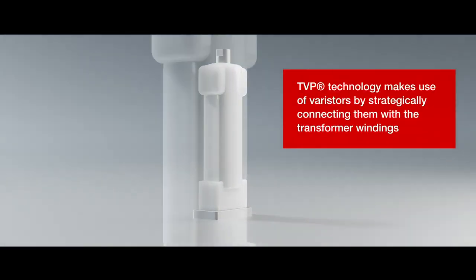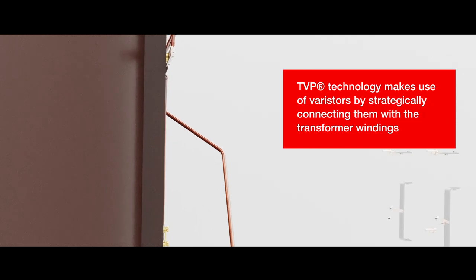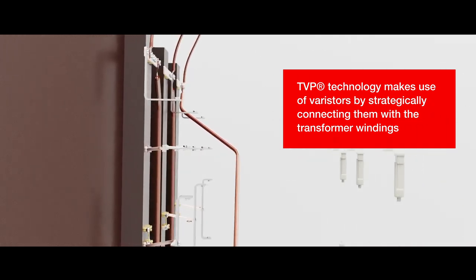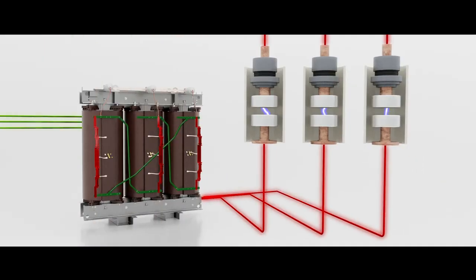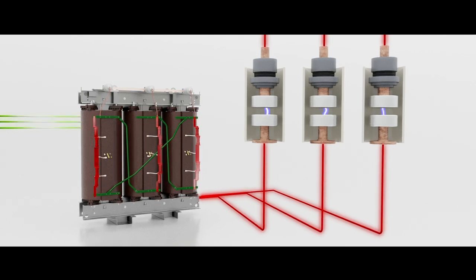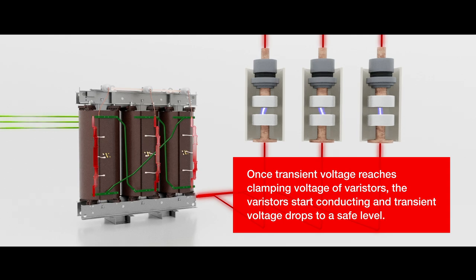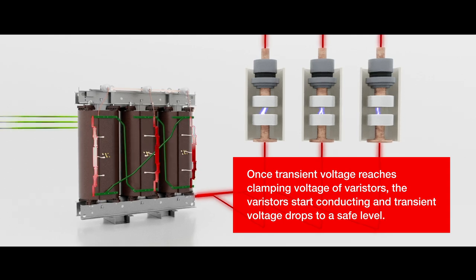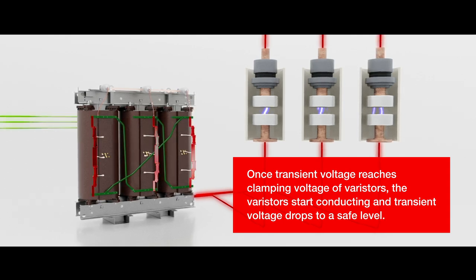TVP technology makes use of varistors by strategically connecting them with the transformer windings. When high-voltage transients are present, the varistors get activated to restrict the destructive transient voltage to a safe level, protecting the transformer from transient voltages.